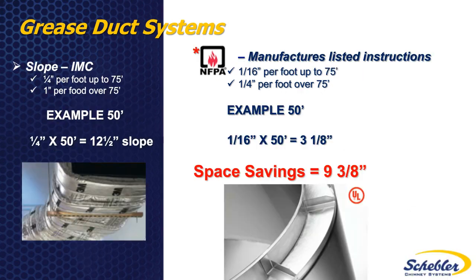So let's compare field fabricated versus factory. If I've got a field fabricated product and I need to comply with the International Mechanical Code, if I've got a 50-foot horizontal run, and per International Mechanical Code my pitch requirement is a 1/4 inch per foot, this is going to require this grease duct to slope 12.5 inches over that 50-foot run. Now, if I utilize a UL listed manufacturer's product and can refer to their installation instructions, as noted in NFPA 96, that same 50-foot horizontal run at a 1/16 of an inch per foot would only require me to have 3 1/8 inches of slope. So in essence, I would save almost 9.5 inches in the overall length of that ductwork just by utilizing a factory built product versus field that would require much less slope.